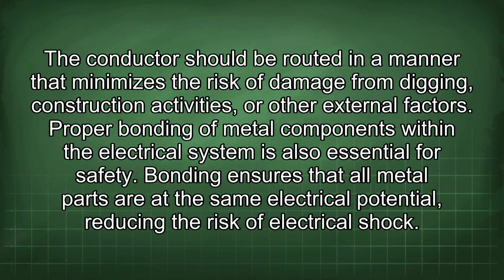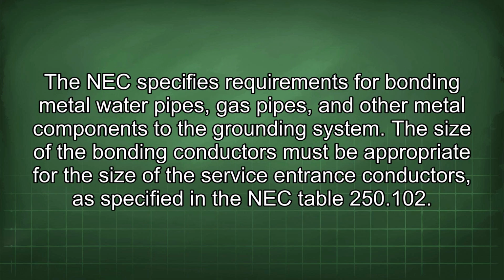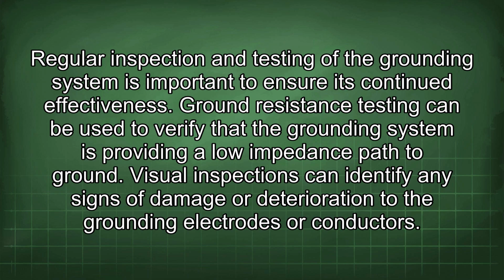Bonding ensures that all metal parts are at the same electrical potential, reducing the risk of electrical shock. The NEC specifies requirements for bonding metal water pipes, gas pipes, and other metal components to the grounding system. The size of the bonding conductors must be appropriate for the size of the service entrance conductors, as specified in the NEC Table 250.102. Regular inspection and testing of the grounding system is important to ensure its continued effectiveness.